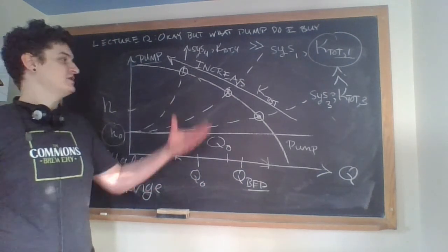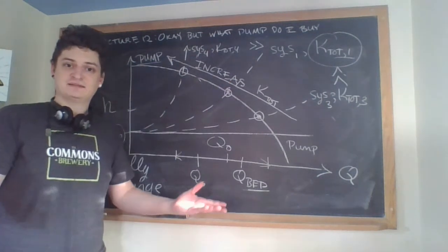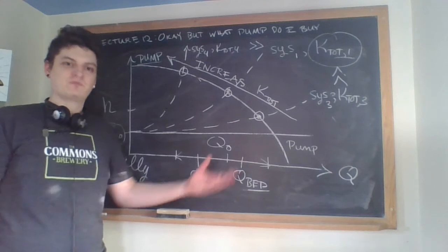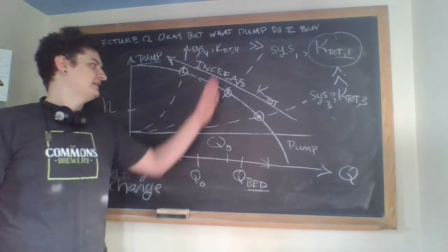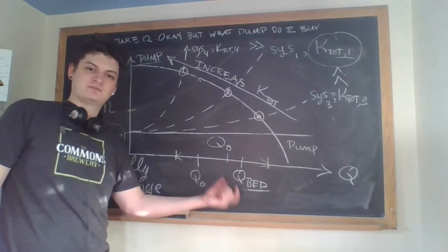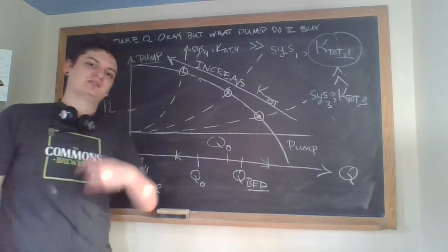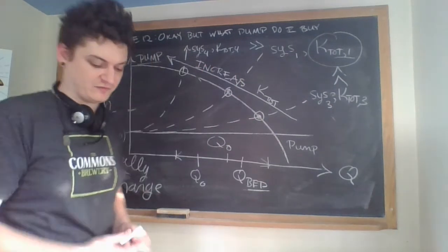for my system. Say you couldn't actually change anything about the system because it's too expensive. Well, then you'd be looking at getting a pump that gets these 2 things close, because these 2 things being close means money savings. You're not wasting a bunch of power going into unused power transfer into your fluid.